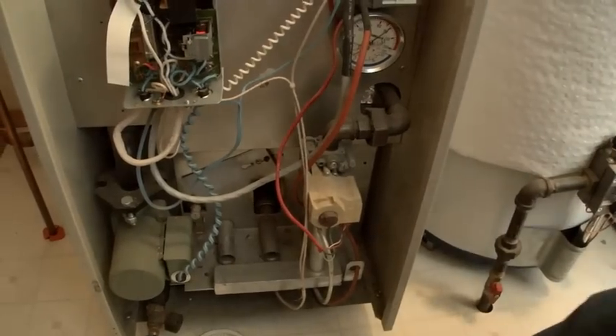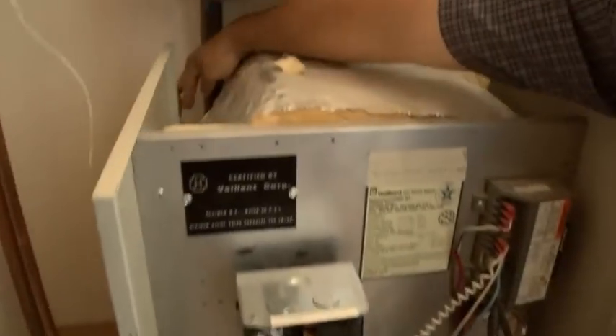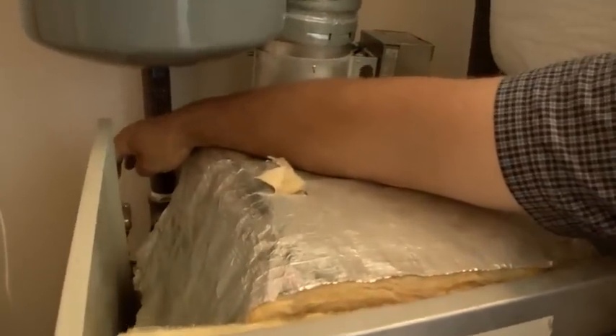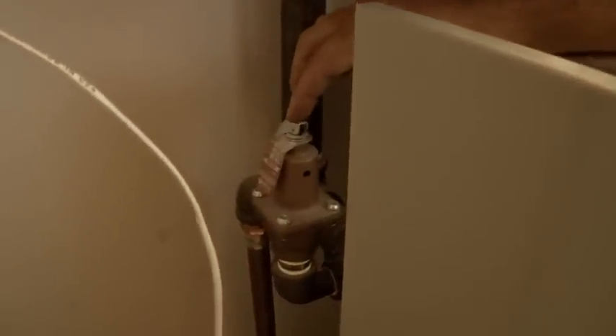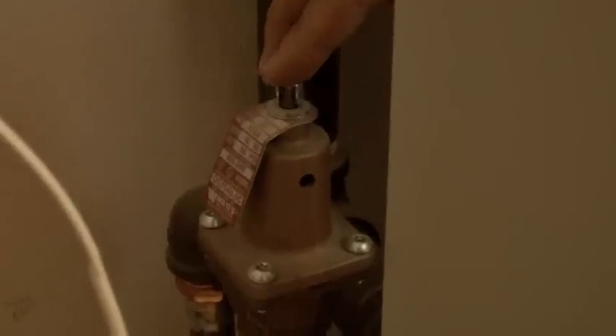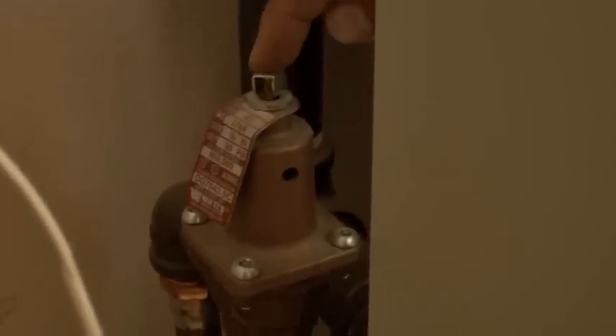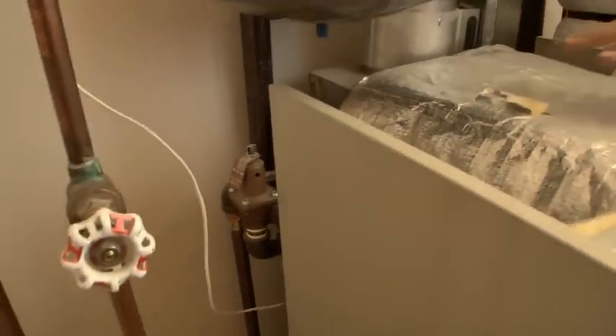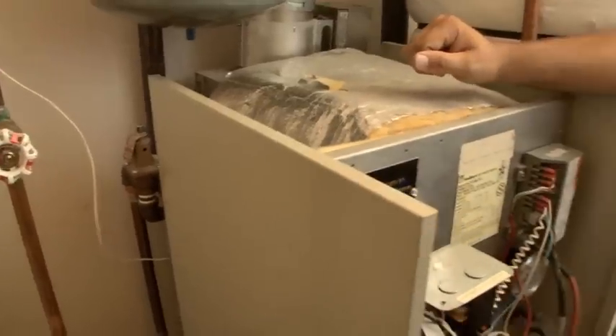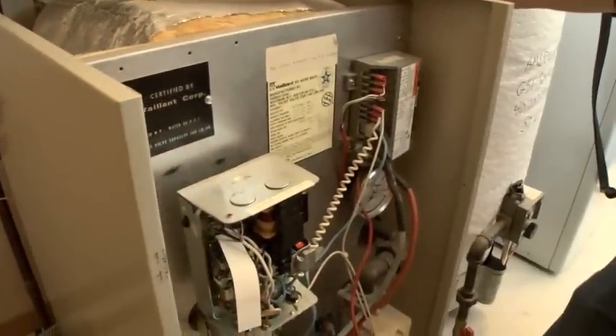Back to that pressure, if we get close to 30, we have a relief valve back here. This valve right here, this is a 30 psi relief valve. When the pressure gets above 30 or right at 30, this starts to relieve water out of the system to eliminate pressure so that we don't create a high pressure boiler here.